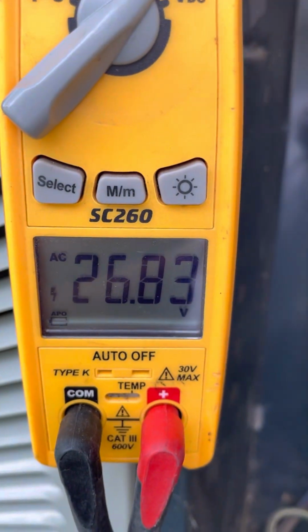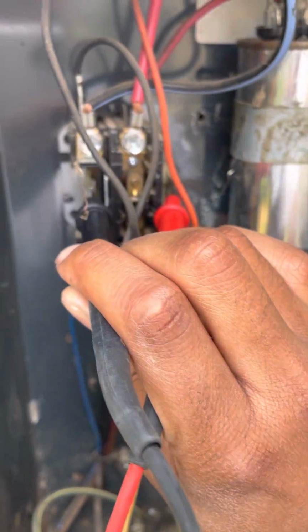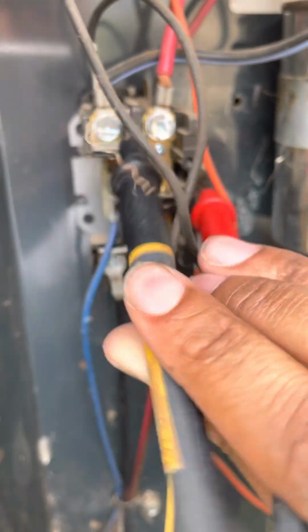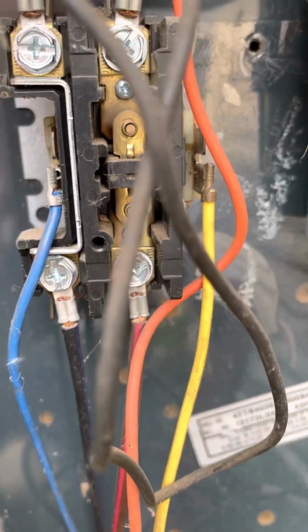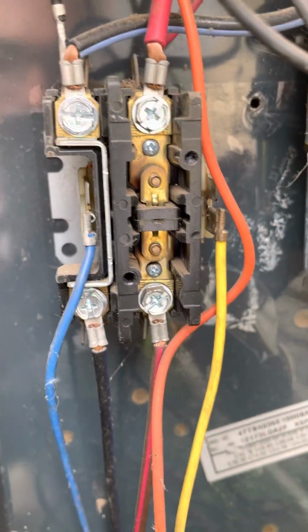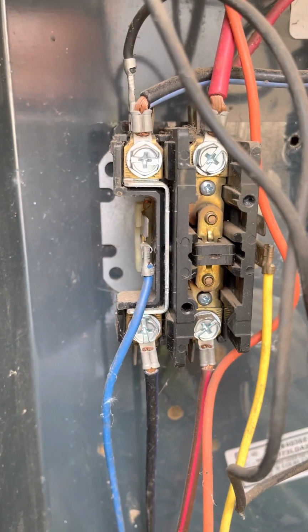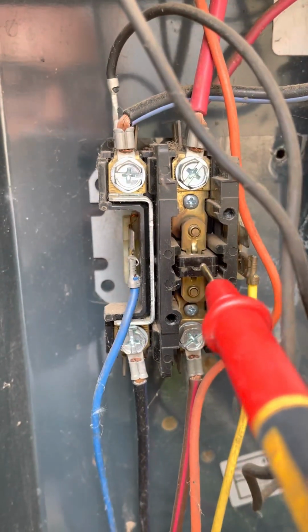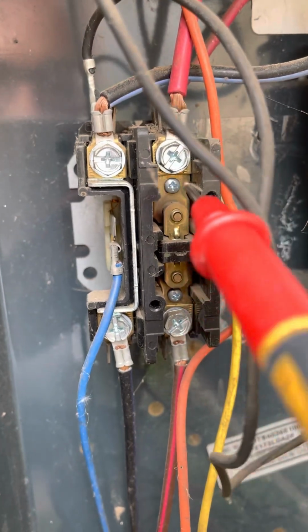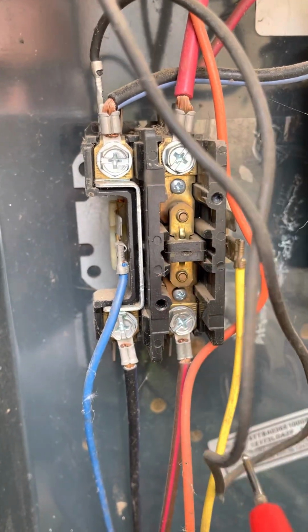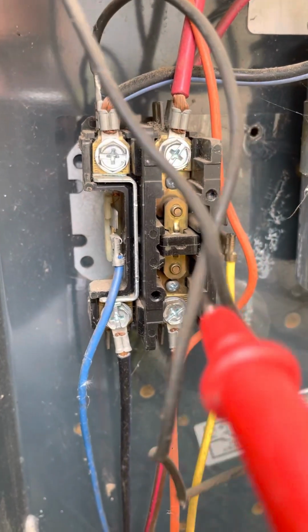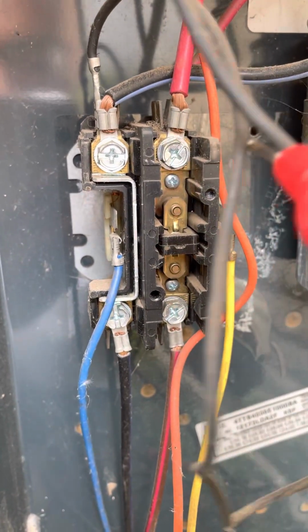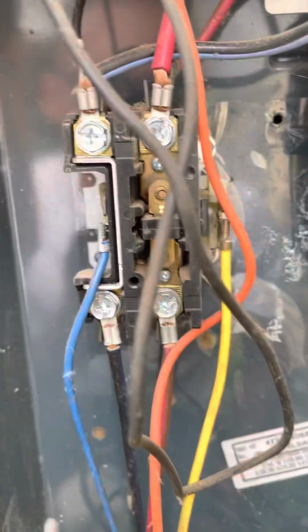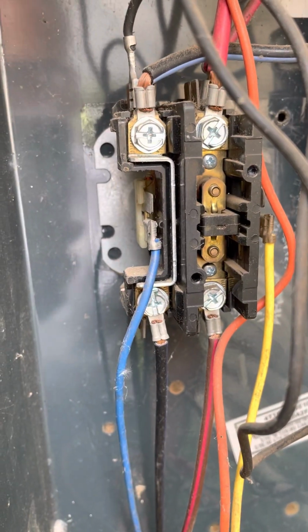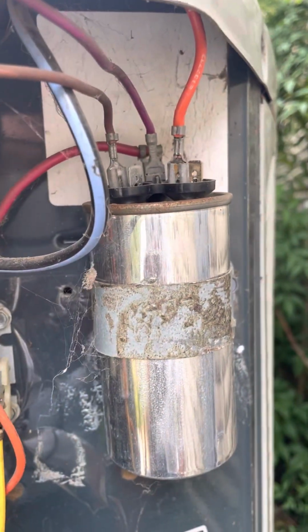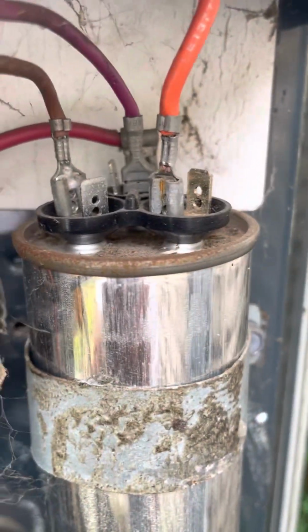There you can see we have about 26 volts, and that's on the coil. So whenever the coil is energized, an electromagnetic field is generated, and that electromagnetic field pulls in this plunger right here and closes the contacts and allows current to flow through and complete the circuit into the compressor. So that's how you do that. But let's move on to the capacitor here.